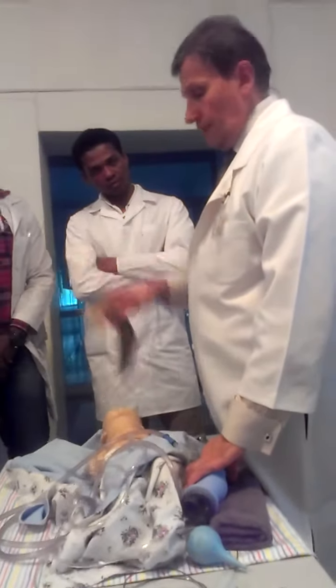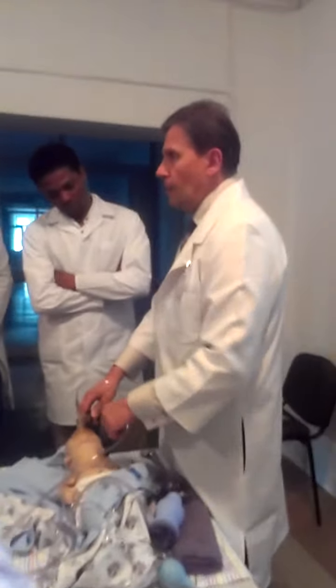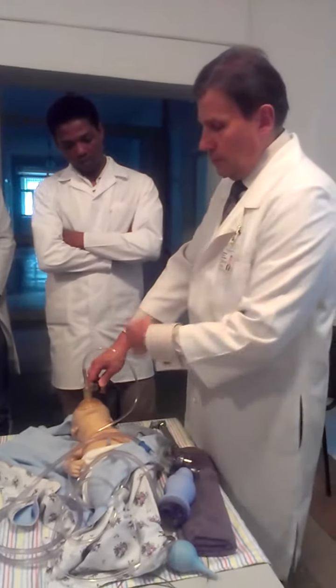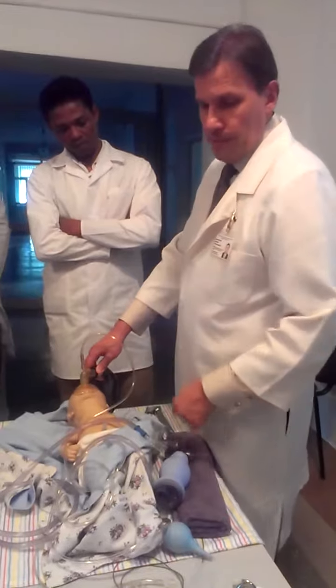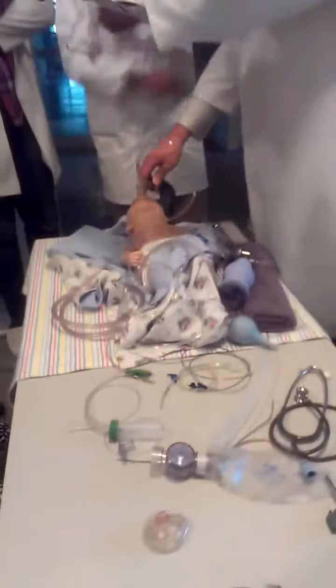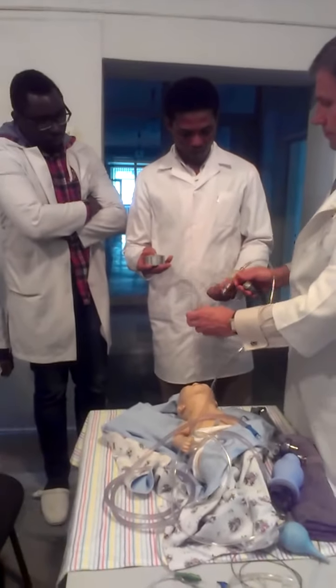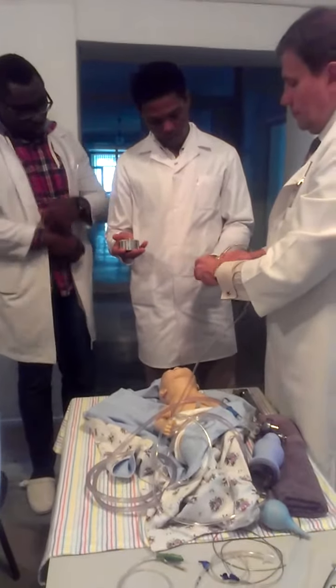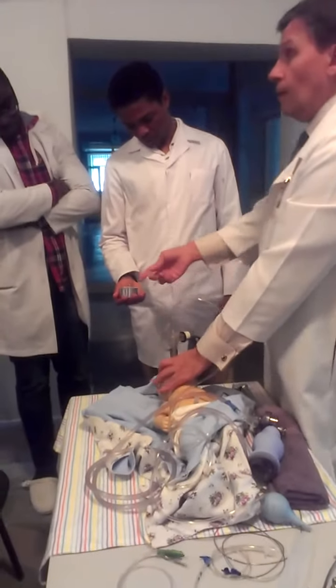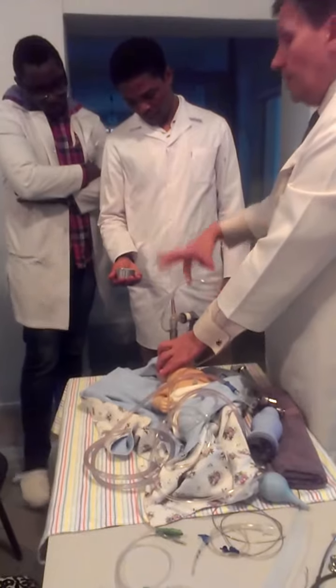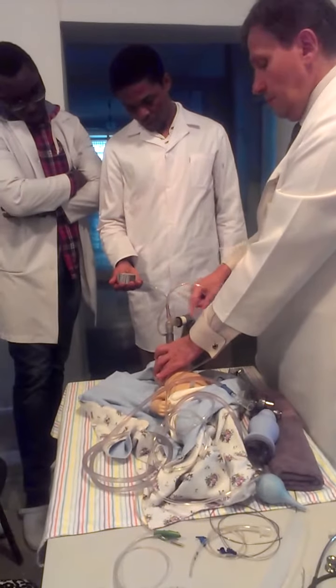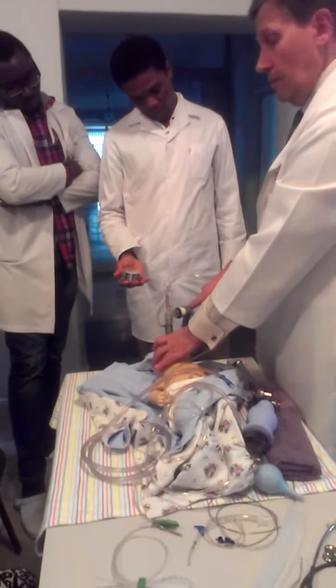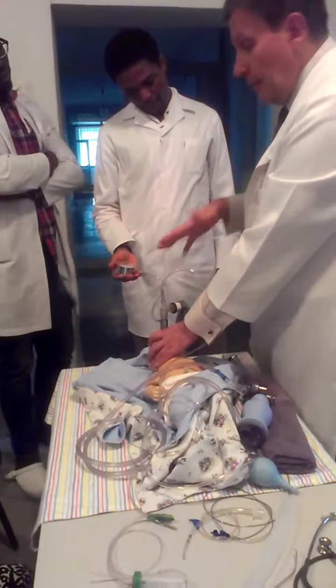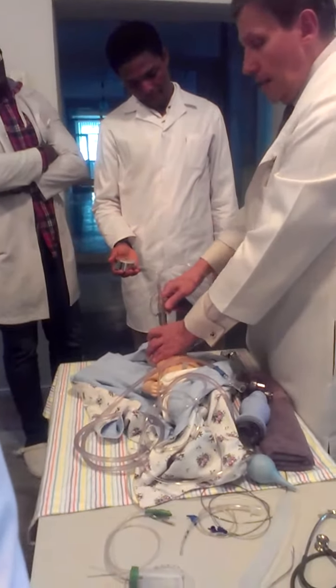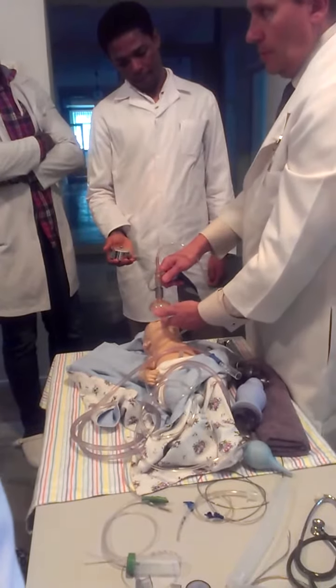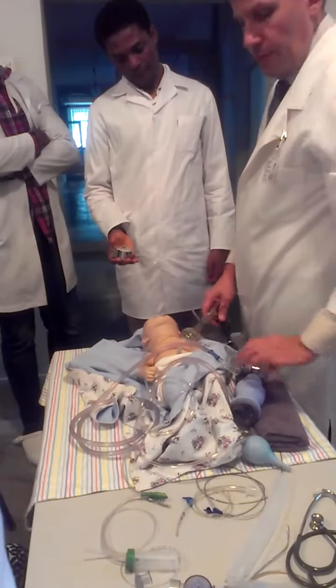Another advantage of this bag, if you put it like this and create a seal, you already have CPAP. Okay, because it's constant flow, and this flow creates pressure. And you may use this device. Yes, and now you will see CPAP pressure. And if you need, you may immediately start ventilation, because bag will be inflating with this. Okay? And this is CPAP, and if you need to resuscitate, you may start ventilation immediately. Again, if you remove this like this, you have oxygen coming to the baby. All this impossible with this bag.